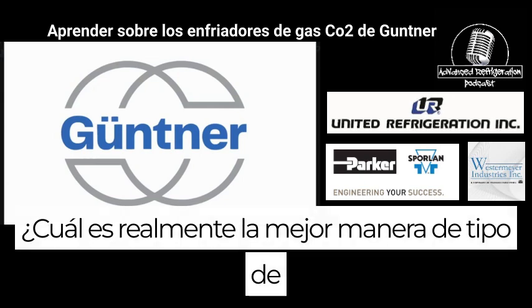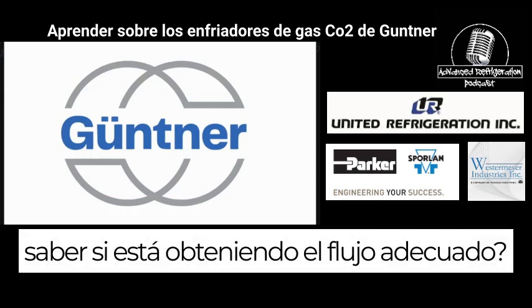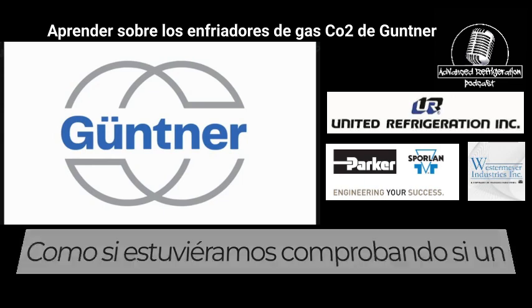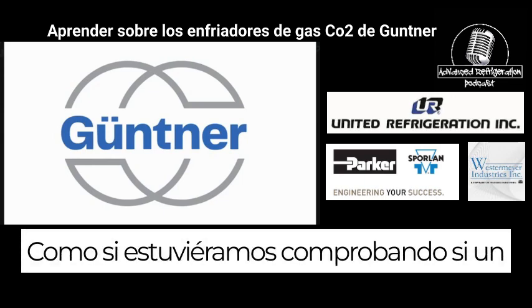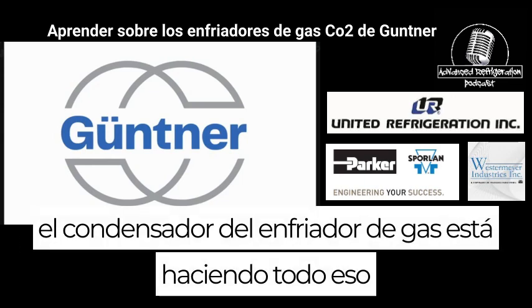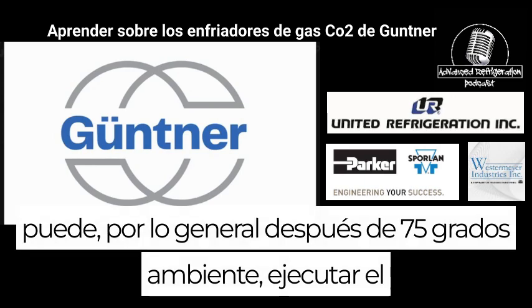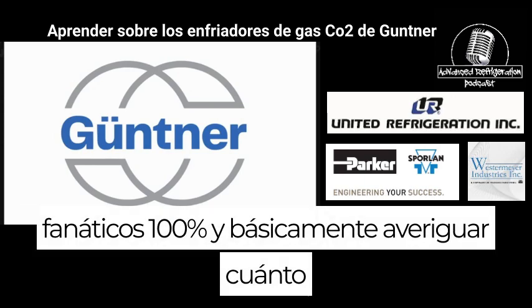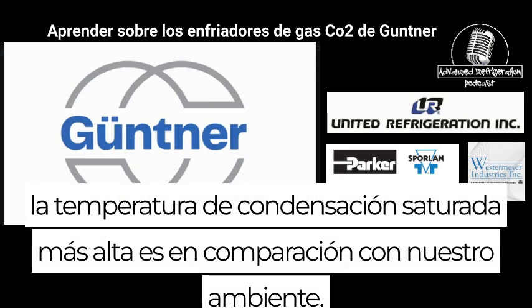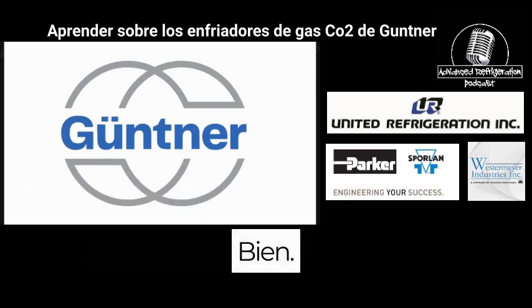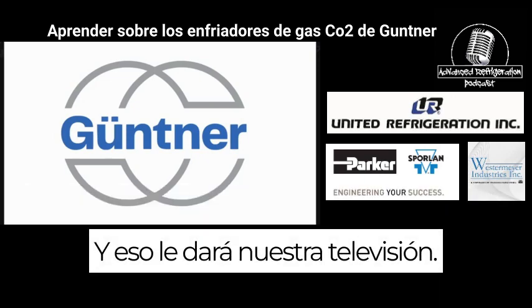What's really the best way to tell if you're getting the proper flow? Like if we're checking to see if a gas cooler or condenser is doing all that it can? Typically after 75 degree ambient, you run the fans at 100% and find out how much higher the saturated condensing temperature is versus our ambient, and that'll give you our TD.